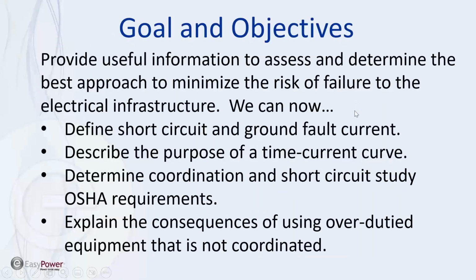Okay, so hopefully we have a better idea of what the risk is, or how to minimize the risk of failure to our infrastructure. It is an important part of what we do and what we need to do. If you've done an arc flash study and you do it every 5 years, you're doing a coordination and short circuit study. One thing you've got to be careful of when you get an arc flash study done: it's not done, labeled, and you're all set, you're good to go.